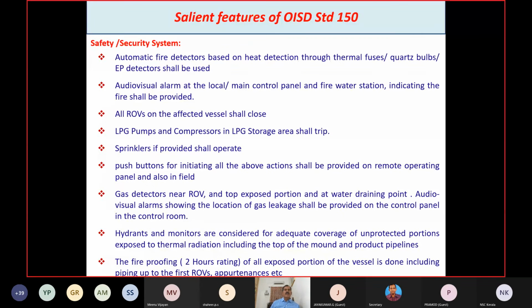Safety and security system for mounded bullets. Automatic fire detectors based on heat detection through thermal fuses and quartz bulbs shall be provided. An audio-visual alarm at the local main control panel and fire water station indicating the fire shall be provided, and all ROVs on the affected vessel shall close.